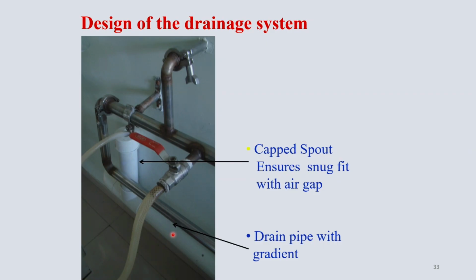Now, if the drain pipe is dipped into that spent dialysate when the machines are switched off, as I told most of the batches, you will have bacteria migrating back along the pipe and into the hydraulics of the machine. So there should be an air gap where the drain line is connected to the drainage system. So we install those capped spouts over there, so that the end of the pipe dips in and is held in place by the capped spout, and there is an air gap between where the dialysate is falling and where it is accumulating. So you would prevent contamination of your machine by that.